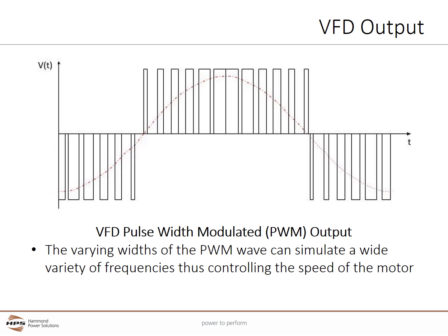The output of a VFD uses semiconductors to quickly switch the voltage on and off in a pulse width modulated or PWM output. By varying the width of the DC pulses, a VFD can simulate a wide range of frequencies from near 0 Hz to several hundred Hz and therefore control the speed of a motor. This PWM wave can have some unintended consequences, which can cause problems with cabling and the motor that we will discuss later.